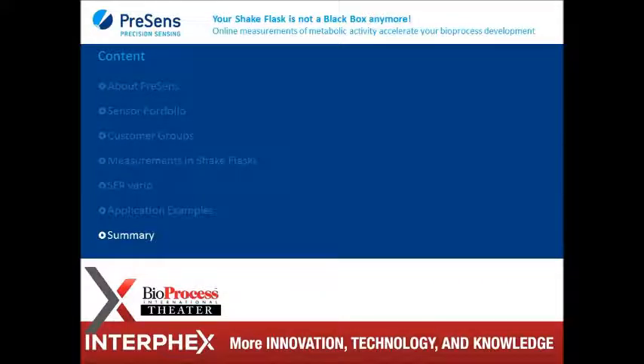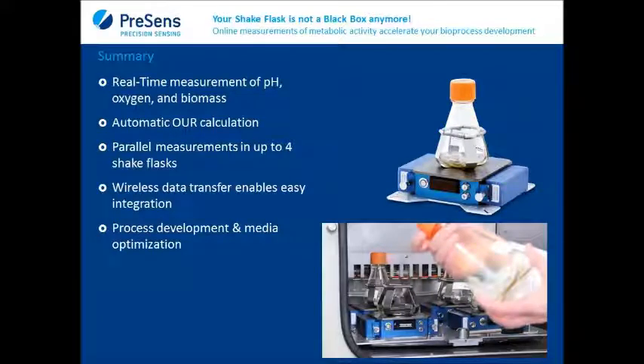So in summary, here on this show we're focusing on our new instrument, the Shake Flask Reader Vario. It's an instrument fitting in any commercially available shaker. You do not have to do any modifications to your existing equipment. You can measure dissolved oxygen, pH, and biomass online in your shake flask. You measure through the wall of your shake flask. You do not have to open it. You do not even have to open your incubator because it has wireless Bluetooth communication to our software. It's a real-time measurement with the oxygen values that you're getting from those measurements. The software can do an automatic oxygen uptake rate calculation as well. You can measure up to 4 devices in parallel. And like I said, it's completely wireless, it's battery powered, and it's definitely a very efficient tool to speed up your bioprocess development or your media optimization.